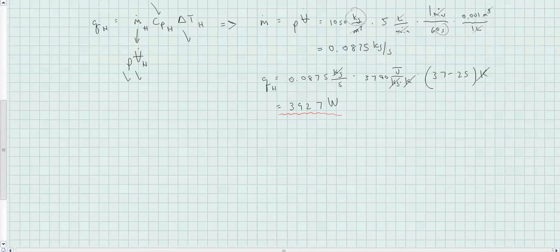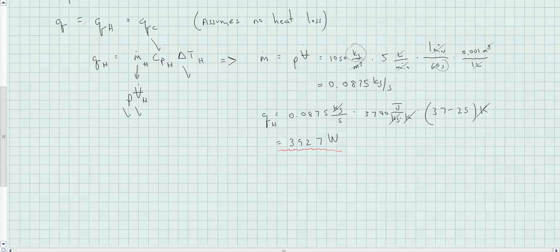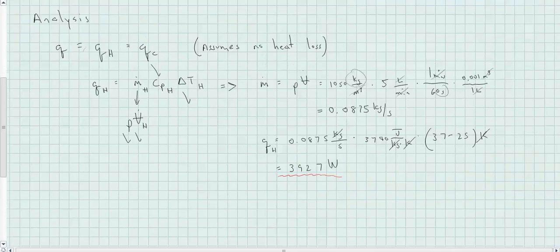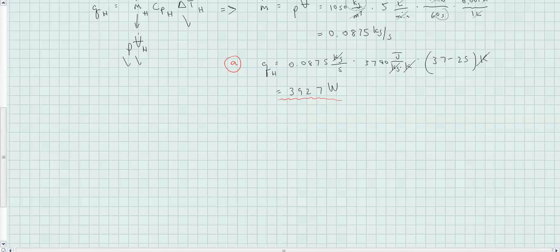So now let's go calculate the mass flow rate and the volumetric flow rate of the coolant, and that's a simple matter. Let's just make sure we label this as solution for A. Now let's go for B, and we can say the Q coolant is the mass flow rate of the coolant times the C sub P of the coolant times the delta T of the coolant.